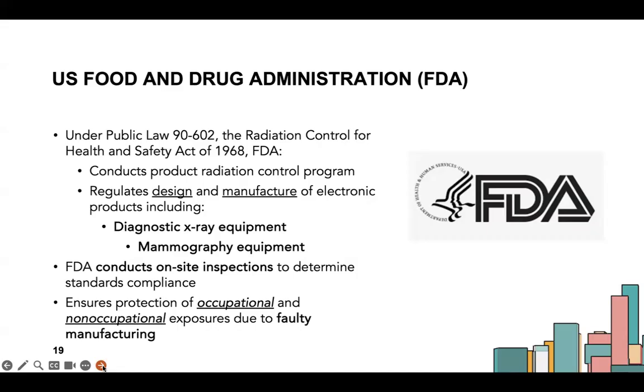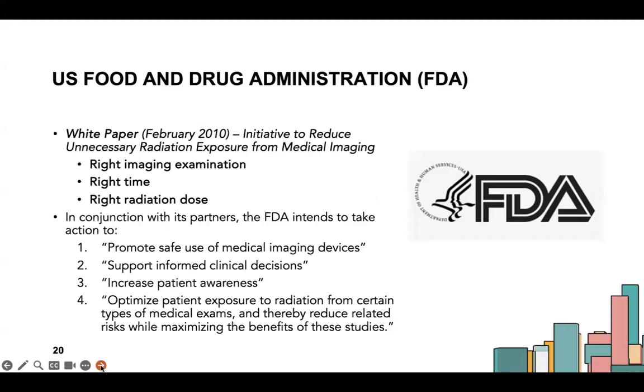So under Public Law 90-602 of the Radiation Control for Health and Safety Act of 1968, the FDA conducts product radiation control. They run that radiation control program that regulates the design and manufacture of electronic products, including diagnostic X-ray equipment and mammography equipment. They conduct on-site inspections to determine if the standards are in compliance, like what I just said, and ensure protection of occupational and non-occupational exposures due to faulty manufacturing. So that's why they're so involved in mammography, because that equipment has to be precise and calibrated in a specific way, because of the sensitivity of the test and what they're looking for.